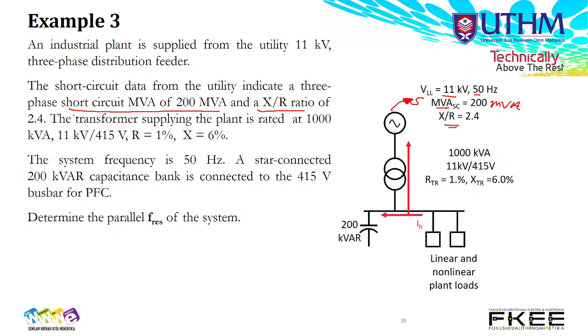The transformer supplying the plant is rated at 1000 kVA. This is the information of the transformer: S, and V line to line at the transformer, given in per unit. In real applications, the data isn't given in ohms but in per unit value. So how do we convert from per unit value to real value?